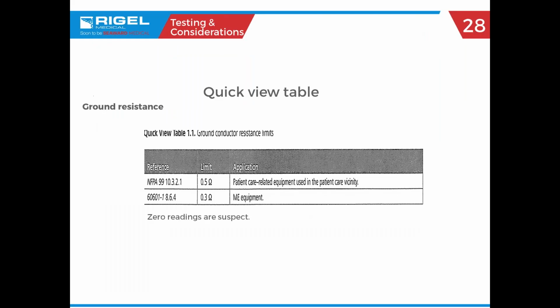So here is an example of a quick comparison. Like we just said, in NFPA 99, you need a reading of less than 0.5 ohms. And 60601 has a stricter requirement of less than 0.3 ohms. So just a little bit of a variance there that you would expect.